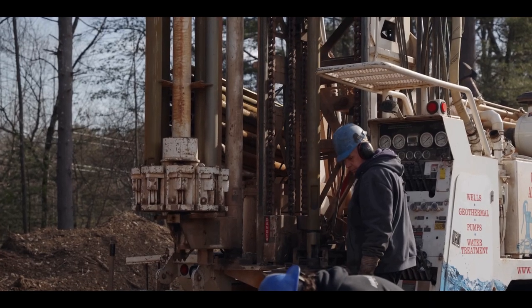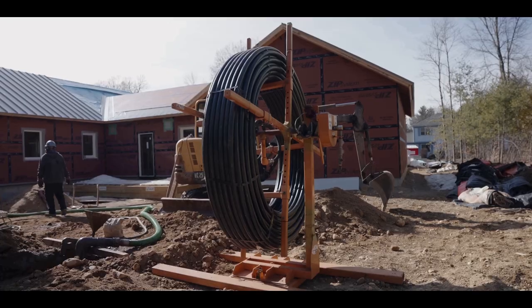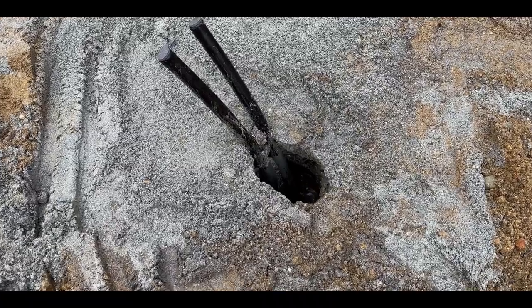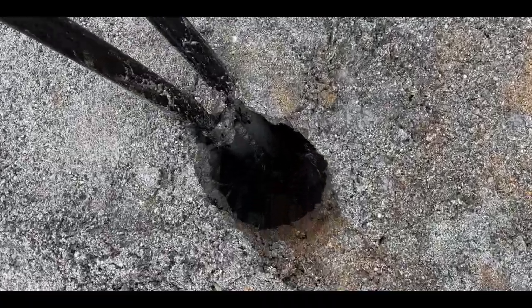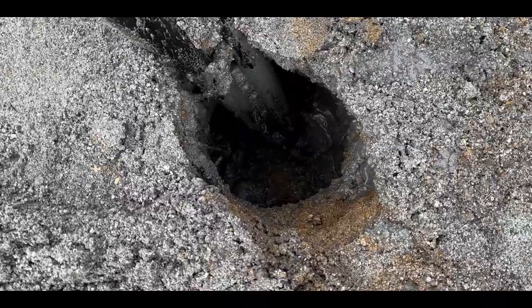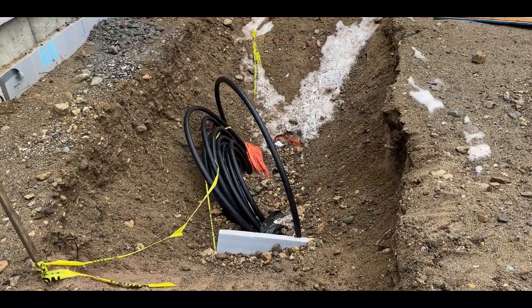After the hole is completed, they feed a closed loop polyethylene pipe into the hole and then fill it with grout. The grout is extremely important because it helps transfer heat from the surrounding rock and dirt into the tubing and ultimately the fluid inside. In my case, they drilled down about 400 feet and only needed one well to support the heating and cooling demands of my HVAC system. Someone else's home might need more wells or deeper wells.